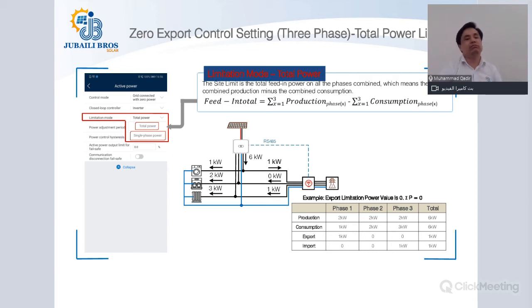In this scenario, since the three phases won't have equal load, there might be a chance that on one of the phases there would be export towards the grid, on one of the phases there could be no export towards the grid, and on one of the phases there could be extra power taken from the grid side in order to balance this whole system. So this is a type of control called total power, which still has the chance of power being exported towards the grid. But in net, if you see how much power is sent towards the grid, it is equal to zero. As in this scenario, 1 kilowatt goes towards the grid, and 1 kilowatt is also taken from the grid side. Thus, the balance is zero.